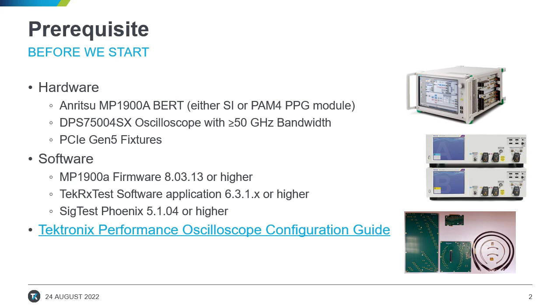We also want to use the latest software and also the automation software, TekRxTest, so that it provides an automated process helping the user make it easier to complete a calibration. So the software: MP1900 firmware, I recommend version 8.03.13 or higher. TekRxTest software application, that is the automation software, I recommend 6.3.1 or higher. And also SigTest Phoenix is required for performing the DSP analysis. We have a Tektronix performance oscilloscope configuration guide that documents all the parts and pieces needed for the Gen5 CEM calibration.